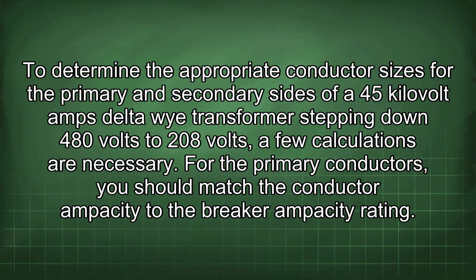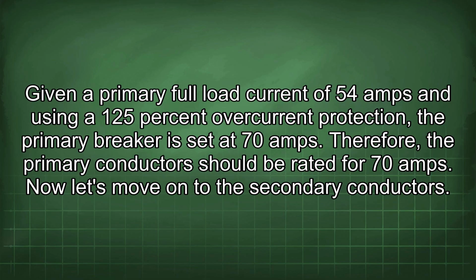To determine the appropriate conductor sizes for the primary and secondary sides of a 45 kVA delta-Y transformer stepping down 480 volts to 208 volts, a few calculations are necessary. For the primary conductors, you should match the conductor ampacity to the breaker ampacity rating. Given a primary full load current of 54 amps and using a 125% overcurrent protection, the primary breaker is set at 70 amps. Therefore, the primary conductors should be rated for 70 amps.